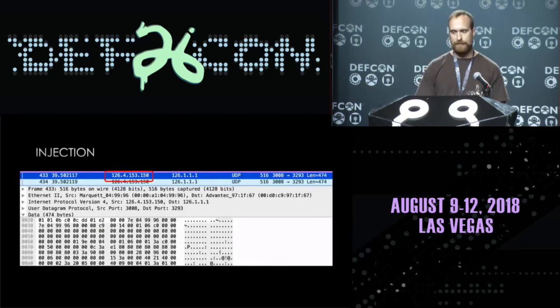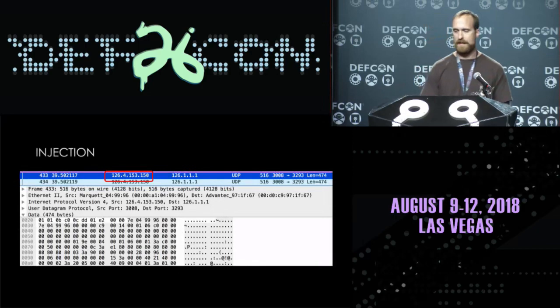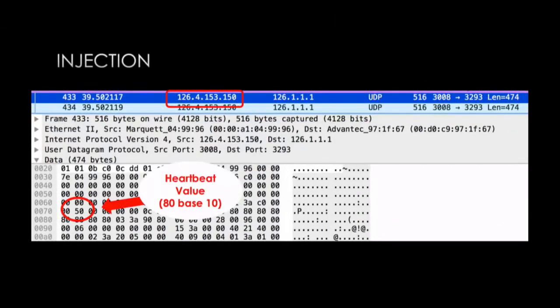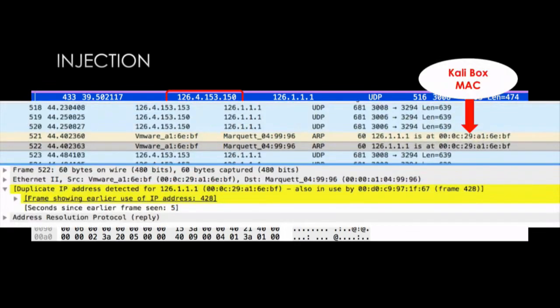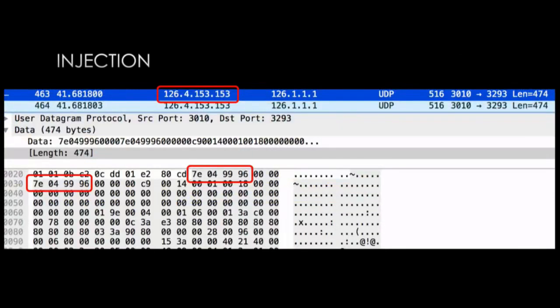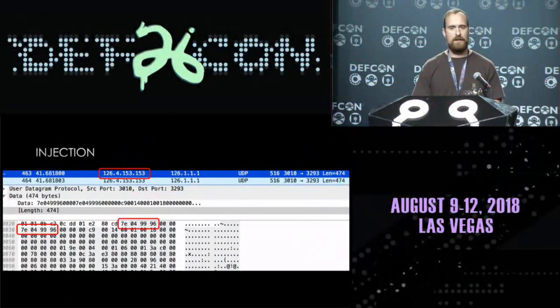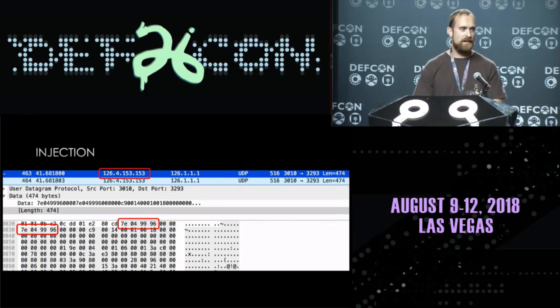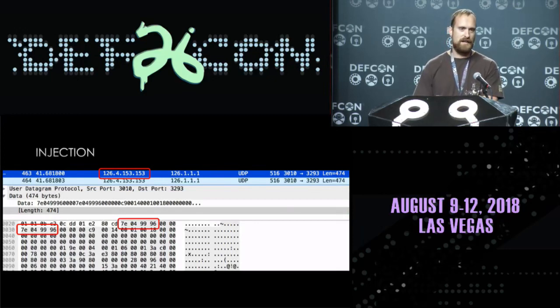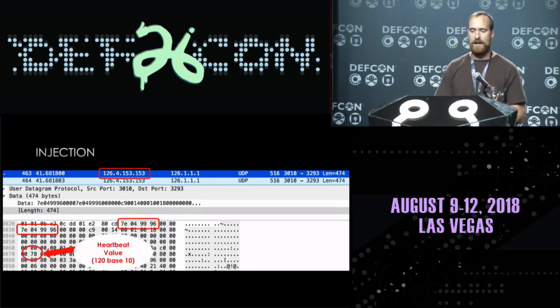What would happen if we ARP spoof the patient monitor, grab the information we need, and then send what we want to send to the central monitoring station? First, the patient monitor at 126.4.153.150 is sending packets across the wire. Since this is unencrypted, we can find that the heartbeat value is stored at offset 71, with a value of 0x50 or 80 in base 10 — 80 as a normal heartbeat. We start the ARP spoof — Wireshark helpfully tells us there's a duplicate MAC address on the network — that's our Kali box. Then, recalling that the IP address is embedded in the payload, it turns out the central monitoring station isn't looking at the IP/TCP header; it's looking at the IP address stored in the payload. So I don't actually have to spoof much of anything — I just leave the original IP address in the payload.